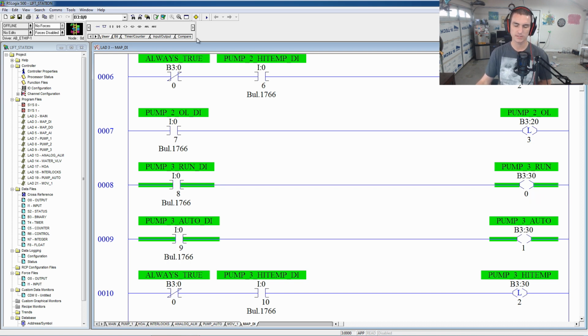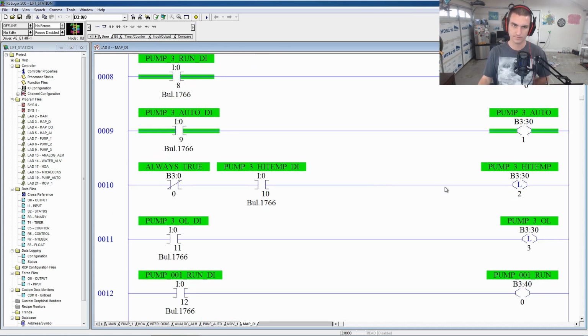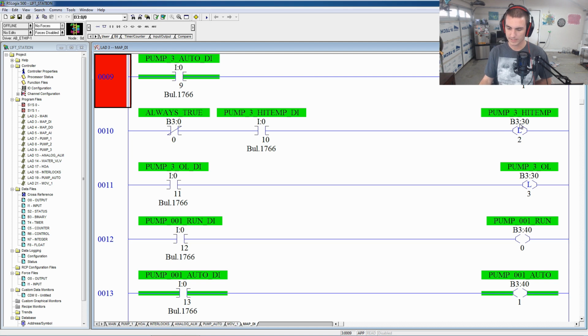What that allows me to do is, it just makes a lot more sense. It's more modular, so you could literally just replace this one digit right here with the pump number. If you had a data type structure, like for example a UDT in Ignition, you could use parameters to parameterize your tags, and you could have 100 pumps and no big deal. Again, this is all much easier on ControlLogix and CompactLogix with logical tag names. So instead of addressing B323, you just say pump2.overload, you know? So it's much more logical. So try to do that if you can, but if not, this is what we're left with. So we might as well make the best of it by making it as nice and neat as possible.